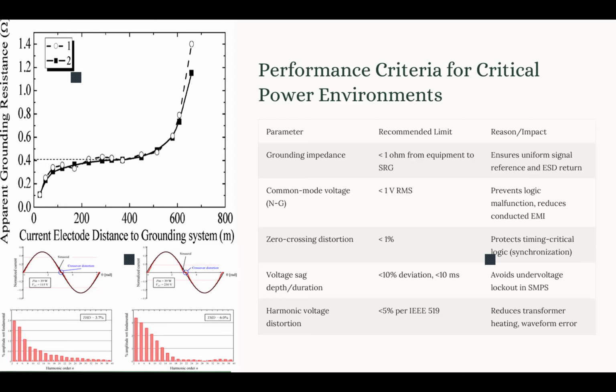Now, we said that our sensitive equipment is also vulnerable to harmonics in the power system. So we have to limit those. We already mentioned briefly the recommended limit for THD is 5%, and we have to define the THD based on IEEE 519. Now, these are basically the limitations recommended by IEEE 1100 for different types of problems that we could face when we talk about the quality of the power system and grounding system in our network and facility.